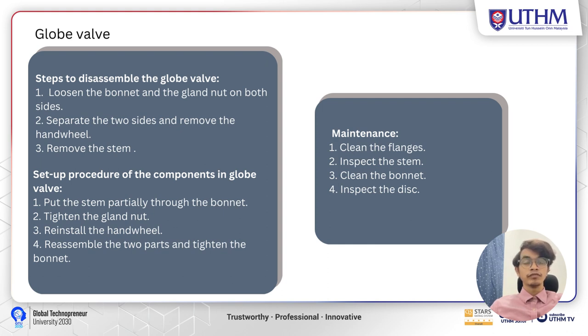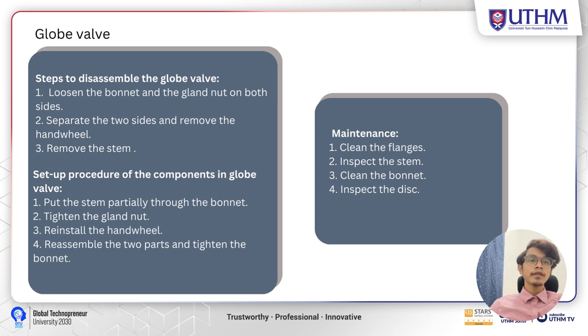For the globe valve, the steps to disassemble are: loosen the bonnet and gland nut on both sides; separate the two sides; remove the handwheel; and remove the stem. To reassemble: put the stem partially through the bonnet; tighten the gland nut; reinstall the handwheel; and reassemble the two parts and tighten the bonnet. To maintain a globe valve: clean the flange, inspect the stem, clean the bonnet, and inspect the disc.